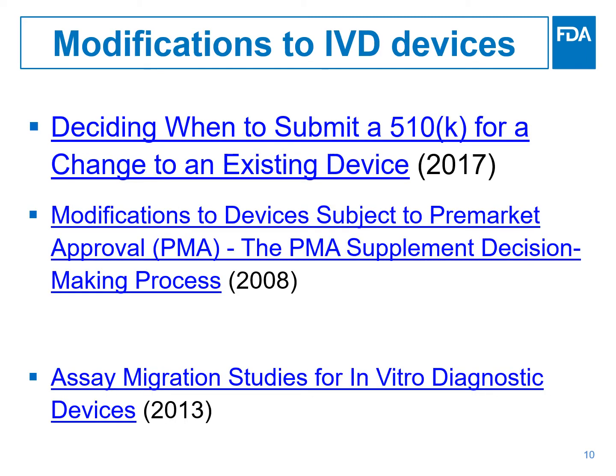The last piece of regulatory knowledge that I think is important for the discussions we will have in December is what FDA requires when a device is modified. In this slide, I'm sharing some of the FDA guidances that provide regulatory advice to manufacturers regarding the requirements for a modification of a medical device.